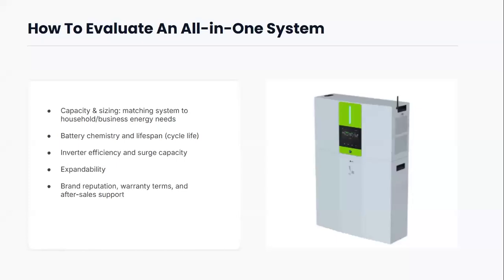All these are part of the system. Inverter efficiency and surge capacity - we need to know the surge capacity of the load we want to put. Is it an AC? Are they just small fans, lightings that will not introduce surge? Because if you don't know that, you may choose the wrong capacity of the all-in-one.